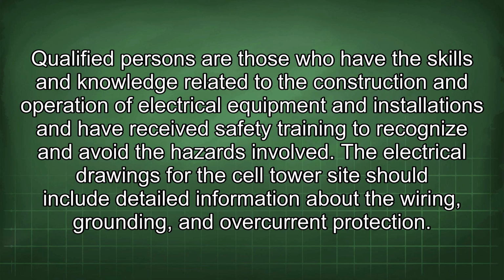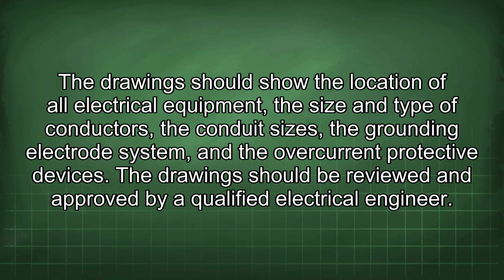The electrical drawings for the cell tower site should include detailed information about the wiring, grounding, and overcurrent protection. The drawings should show the location of all electrical equipment, the size and type of conductors, the conduit sizes, the grounding electrode system, and the overcurrent protective devices. The drawings should be reviewed and approved by a qualified electrical engineer.